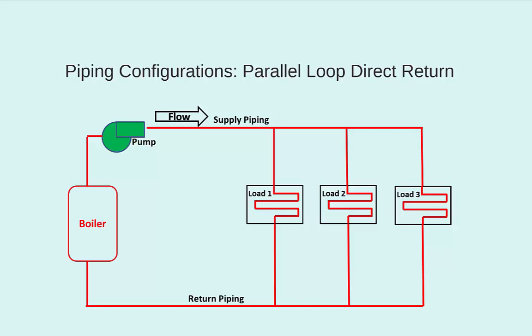There remains an issue here. Say each coil is sized for 10 GPM of flow. That means on the coldest day of the year, each coil would be calling for 10 GPM of flow. Though there are control valves installed at each coil, we would want them operating in a fully open configuration since the system is operating at design conditions. Even though they all want 10 GPM of flow, with all the control valves wide open, more flow is going to travel through the path of least resistance. That path would be through the first coil.